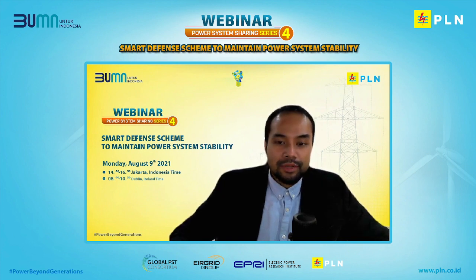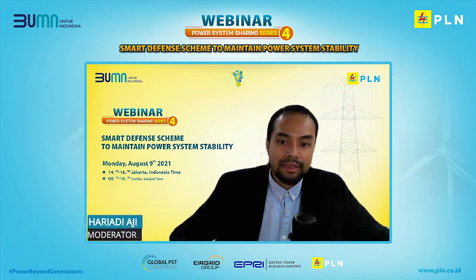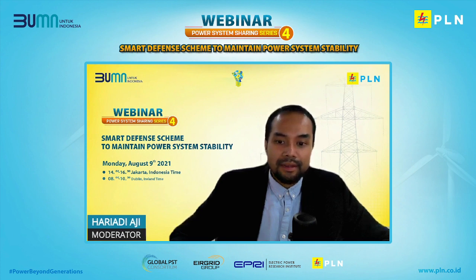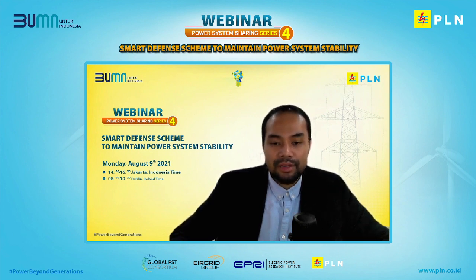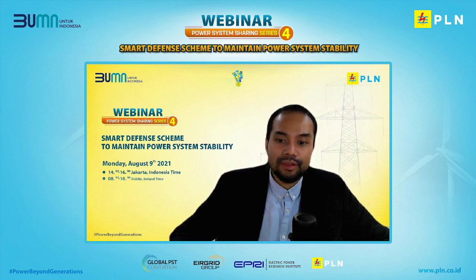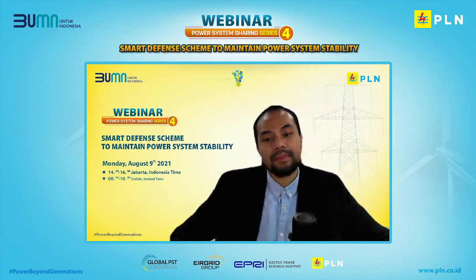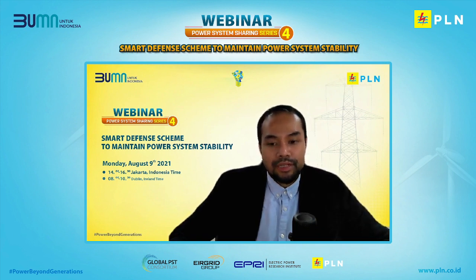The system integrity protection scheme is an automatic grid protection system used to detect abnormal and predetermined system conditions like power swing, and designed to take corrective action other than tripping the faulted component. There were several cases of SIPS misoperating or failing to operate, like in wide area protection schemes in Argentina and other examples, due to slow communication, human error during maintenance, or insufficient guidelines for the operator. It has to be improved. Also, designing a smart protection scheme must consider system operation, system planning, and resilience to failure.